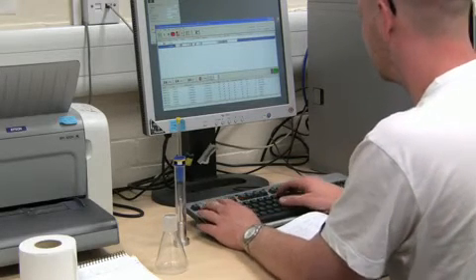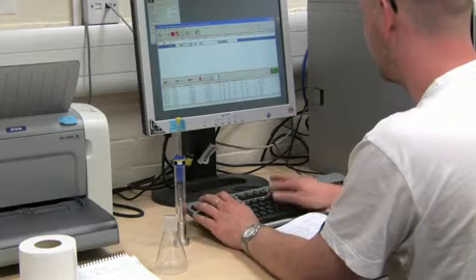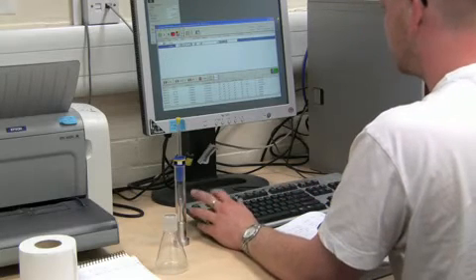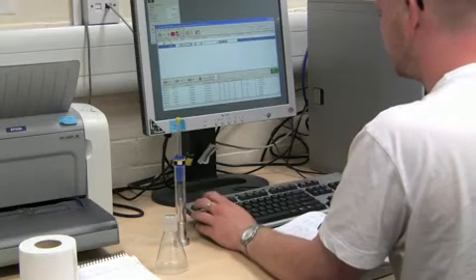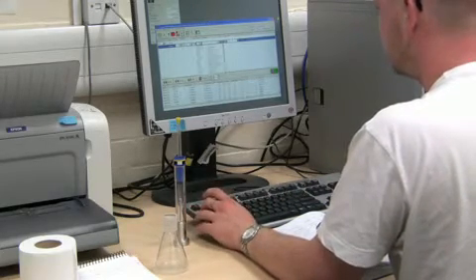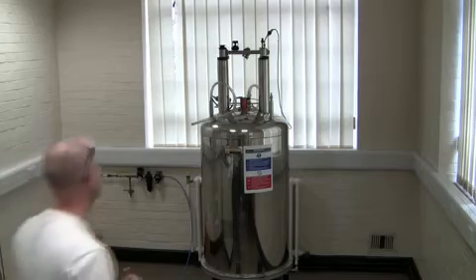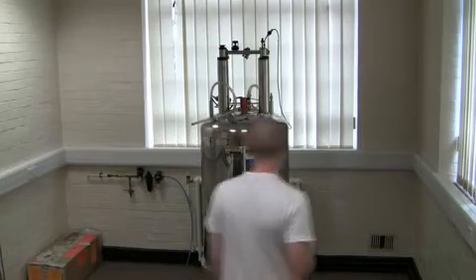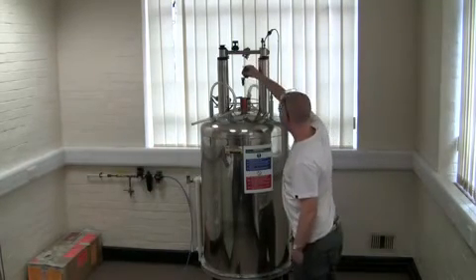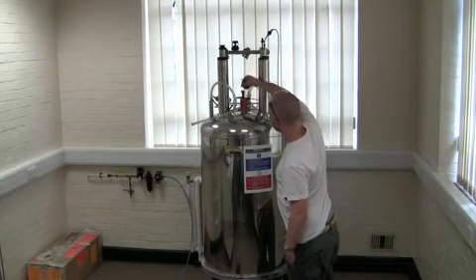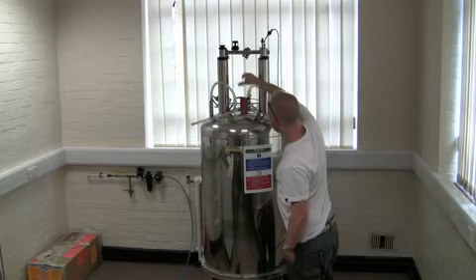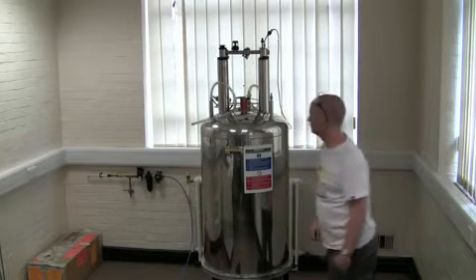The details of the sample to be run are entered onto the operating computer. The sample in the spinner is placed in the instrument above the magnet and lowered into the magnetic field on a cushion of compressed air.